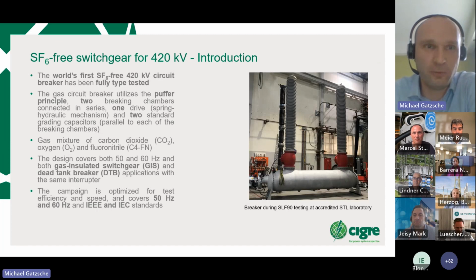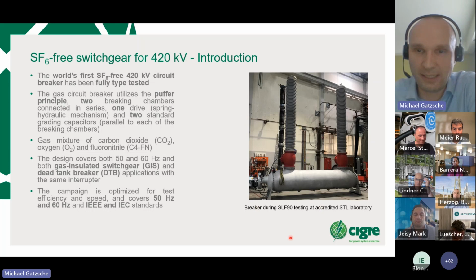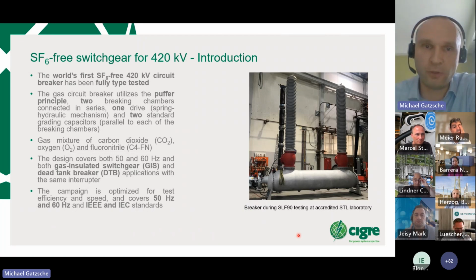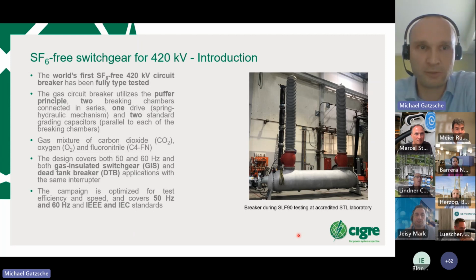Okay, let's start. So what is the story about the SF6 free switchgear for 420 kV? The main story is that the world's first modern SF6 free 420 kV circuit breaker has been fully type tested. You can see it here on the right side in the STL accredited laboratory during the SLF90 test. It is a gas circuit breaker using the puffer principle. It is a double break, so it has two chambers connected in series. Each chamber has a grading capacitor, and it is operated by one drive, a spring hydraulic mechanism. You can see this on the left side because it's a lab test, without the drive cover in this picture.